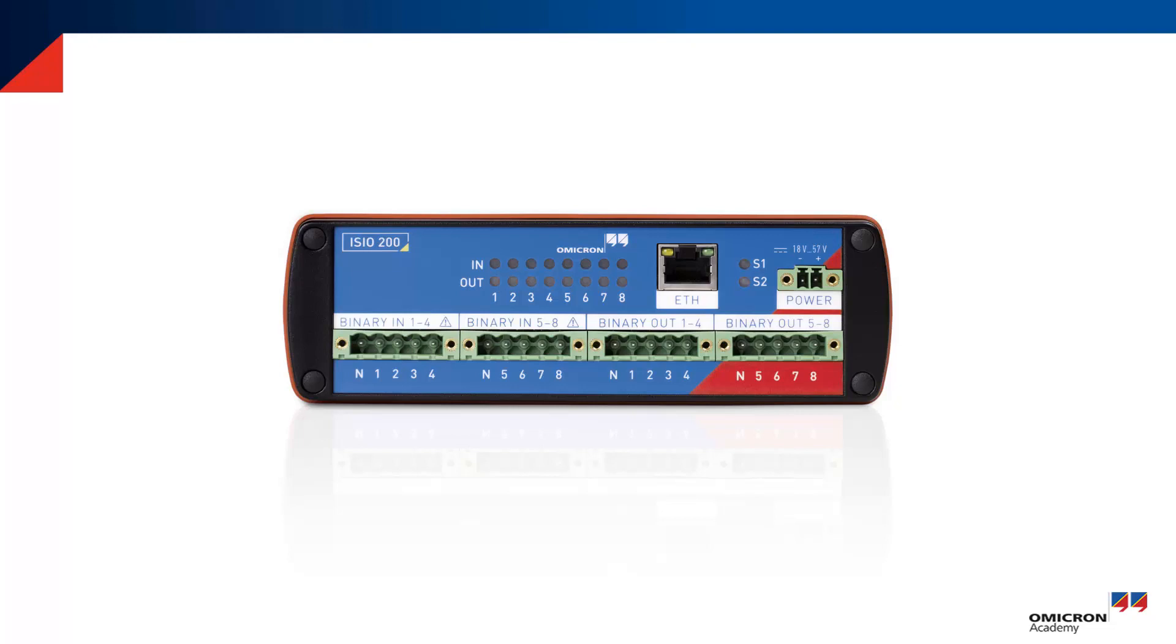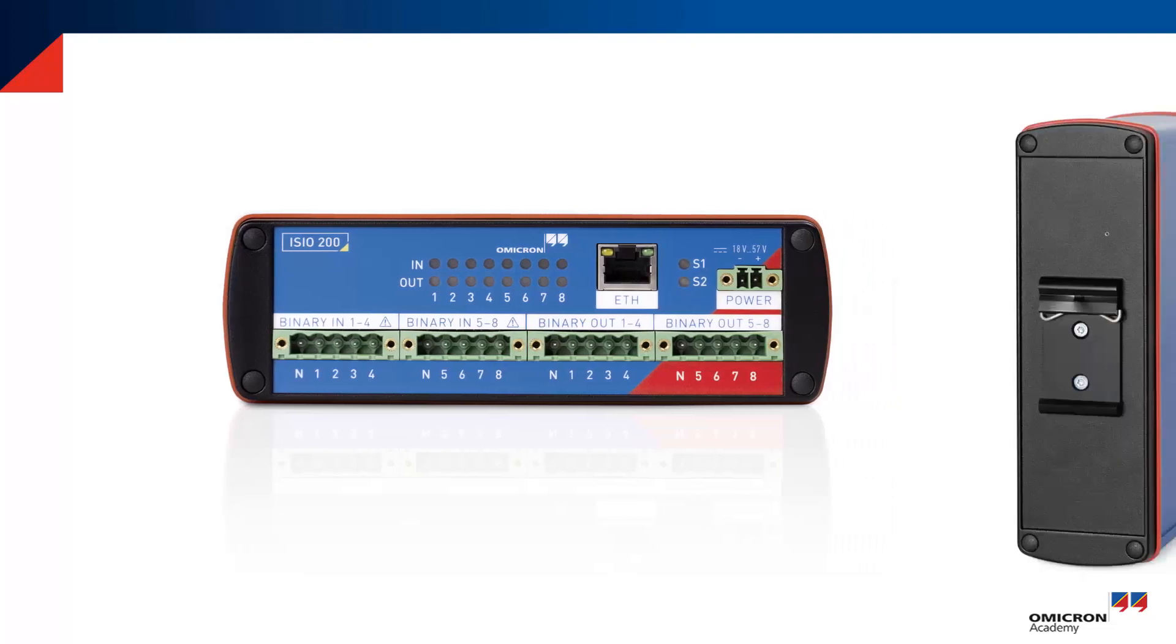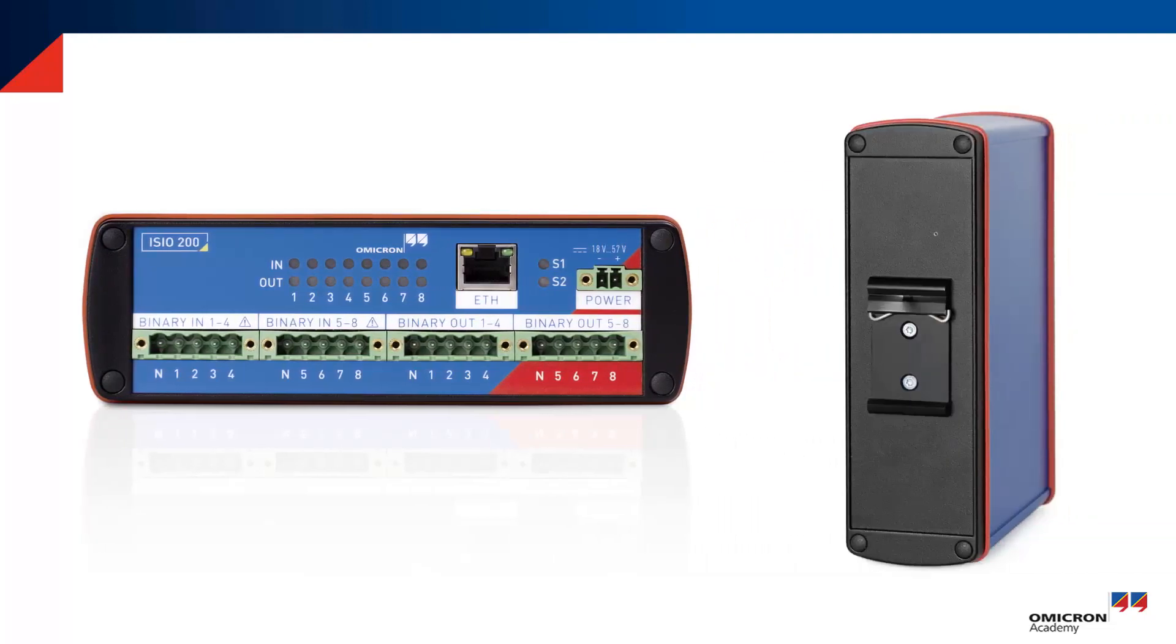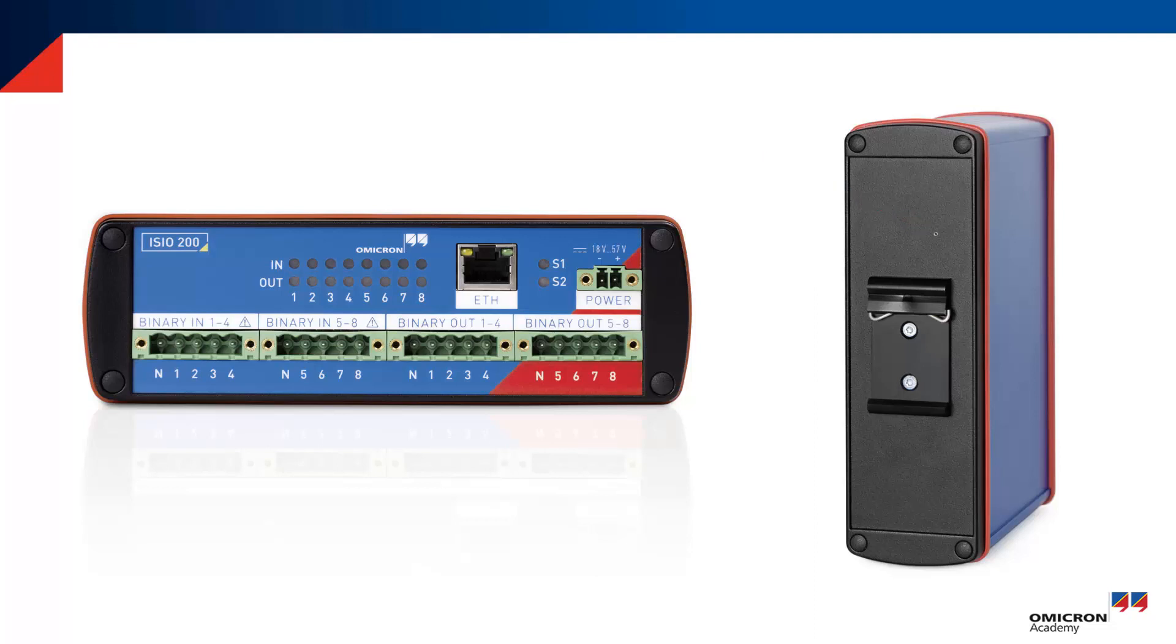At first, iSIO must be prepared to be connected to the CMC. We perform a factory reset by pressing the little button on the back side of the device to delete all previous configurations. The binary input's threshold values are also set to 18V this way.